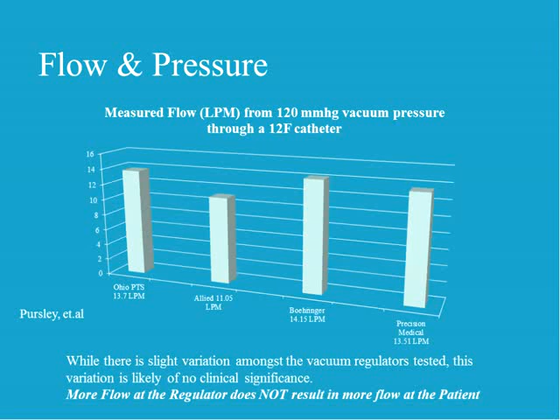And the standards for vacuum regulators, actually, there really are none in terms of flow. What there are standards for by the NFPA is the actual vacuum outlet, and you measure the flow through a vacuum outlet and look at lateral drops in pressure and flow without a vacuum regulator in there.